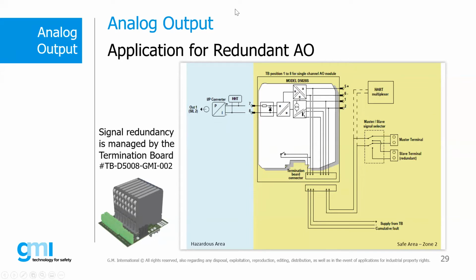In fact, we will have a main common signal called master and a support of it, called slave. The two signals arrive at the terminals of the termination board and at the input of an electronic switch placed on board. If both signals are regular, the master commands the loop and drives our load in the field. When this master signal fails due to a line fault or because the relative analog output card fails, the current signal relative to it goes to zero, and the electronic switch placed on the termination board switches to the slave signal, making sure that the output load continues to be correctly powered.